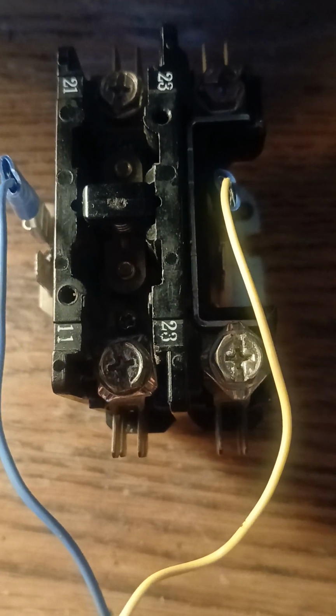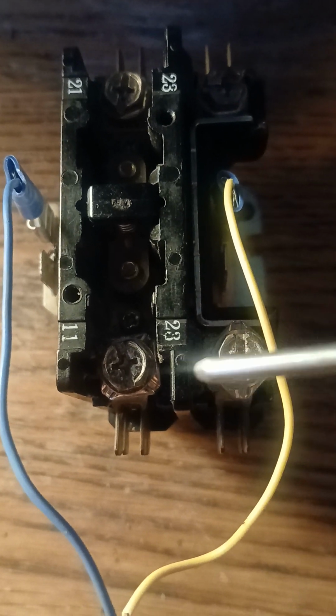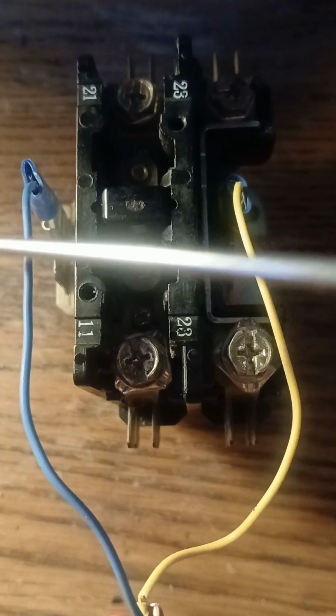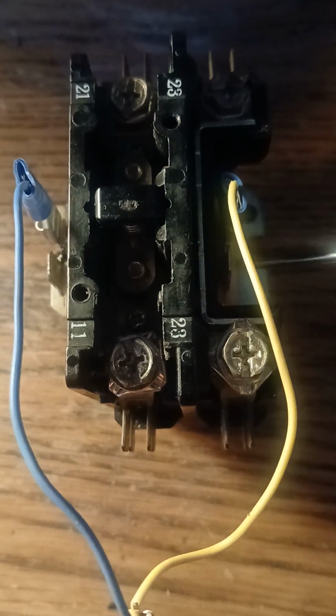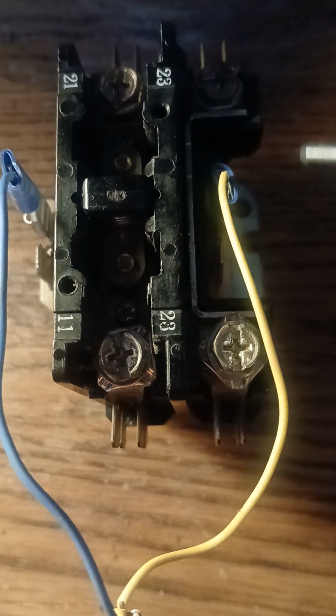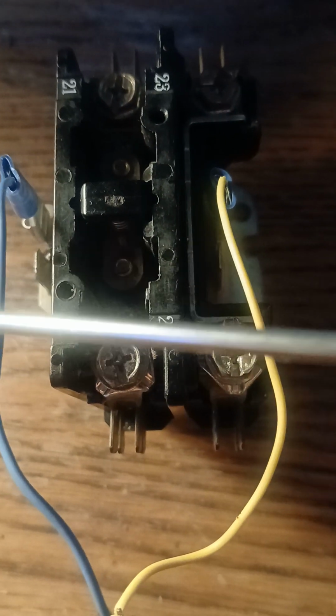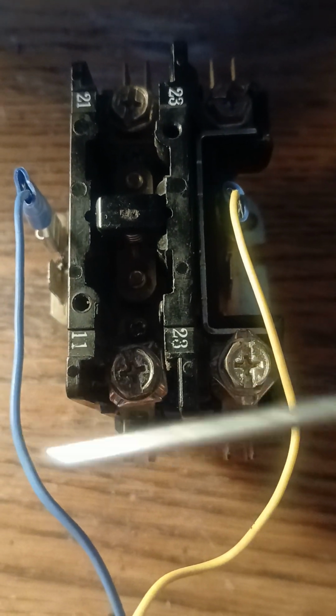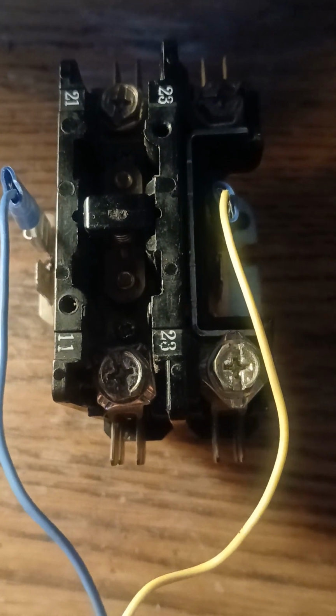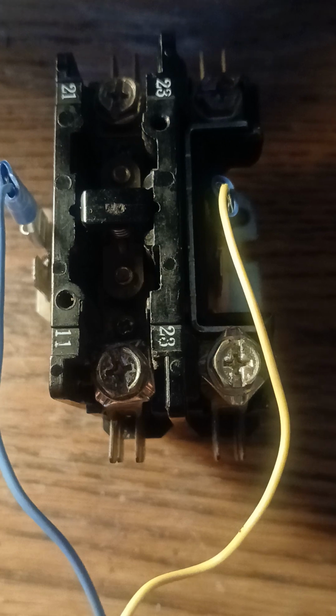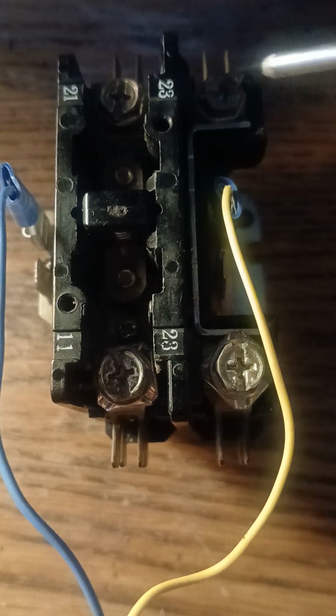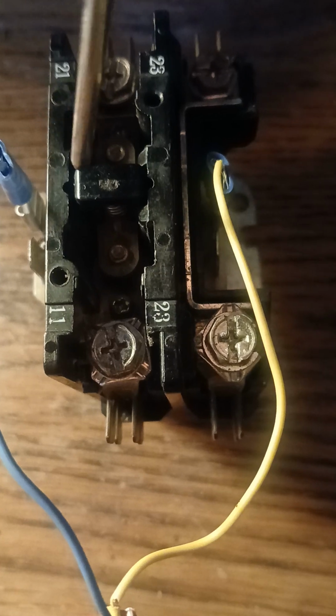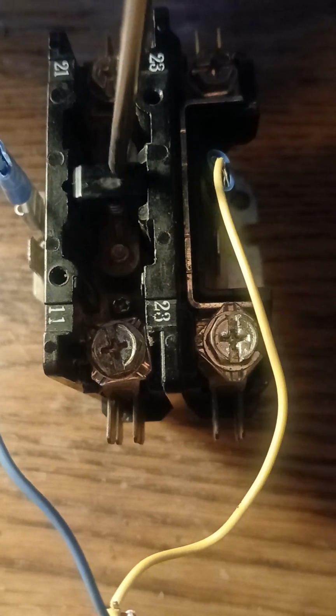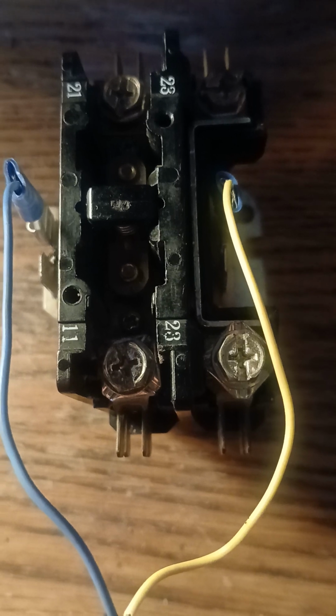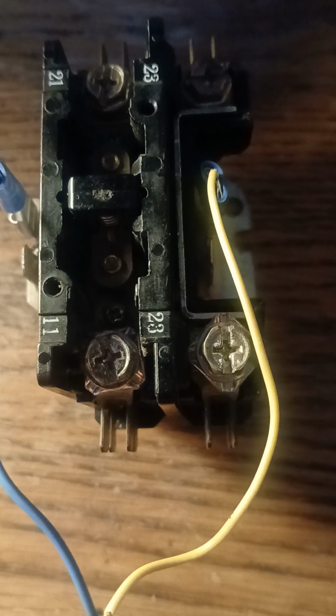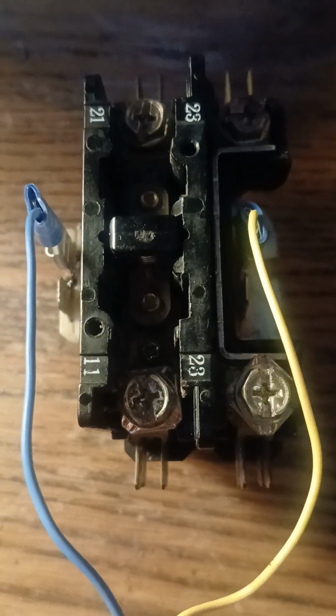It's pretty fairly basic. But again, if you would power this up with 24 volts on the side, this would be your 24 volt side, your low voltage side. The top and the bottom: just think side, both sides low voltage; top, bottom, high voltage; and this would be powering a HVAC contactor. Now, what would happen after this voltage energized? This little plunger would go in, the electricity would go, and then it would give access to the compressor and the condenser fan motor to operate those.